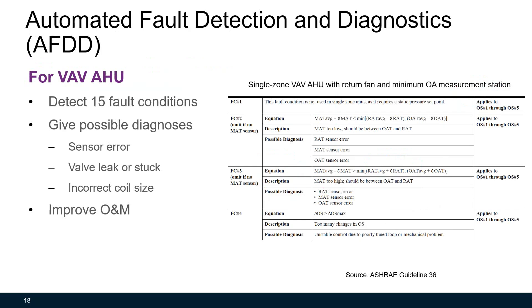This guideline also includes some basic automated fault detection and diagnostic (AFDD) rules based on research by the National Institute of Standards and Technology (NIST). The algorithm should improve the operation and maintenance of HVAC systems. This slide shows a portion of the rule table for a single-zone VAV AHU with return fan and minimum outside air measurement station.